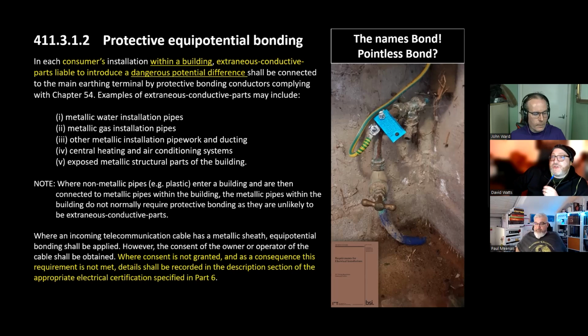Yeah, without any other instruction about things like you say 25 volts, if there's more increased risk, if the person's in a wet room or a location like a bathroom, you'd have to assume, and that's a dangerous word as well, that we're talking about the point of ELV to LV, the 50 volts or the 120 volts AC and DC, because that's what we would do with 415.2 with supplementary protective bonding. We'd do it to ensure that was the voltage we must not go over. With all these other protective functions, that is the point that we must not go over. Unless they give us something more definitive, no, it's actually 25 volts, I'd have to go with that, with my own initial opinion. But again, I could engineer it so it's got a 38 volt touch voltage, but it could be that the way they use the system, that's still dangerous. It's a very dangerous word.